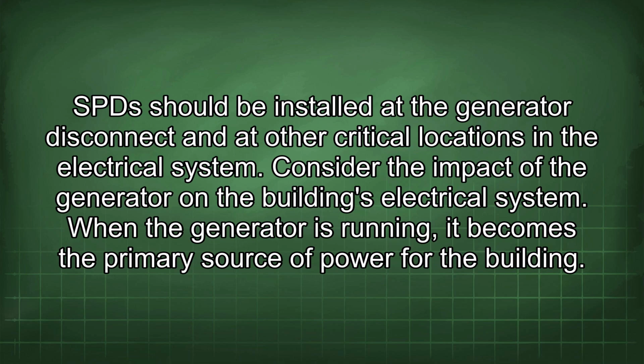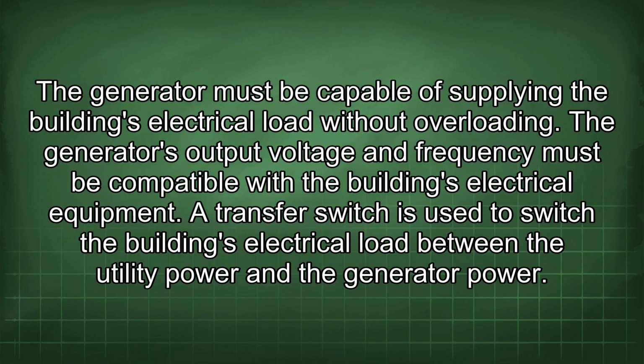Consider the impact of the generator on the building's electrical system. When the generator is running, it becomes the primary source of power for the building. The generator must be capable of supplying the building's electrical load without overloading. The generator's output voltage and frequency must be compatible with the building's electrical equipment.